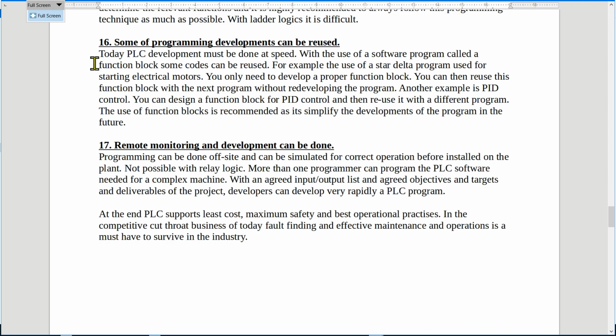For example, let us say that you use a star delta program for starting an electrical motor. It is very difficult to do this program and to actually program it inside the PLC every time you need it. But what you can do is develop a proper function block with the time settings, the enabling of the star delta, etcetera. You can then design a function block, and you can reuse this function block in the next program without redeveloping this program. You can just take the function block, drop it in the program, and actually connect it as required. And we will get to function blocks at a later stage.